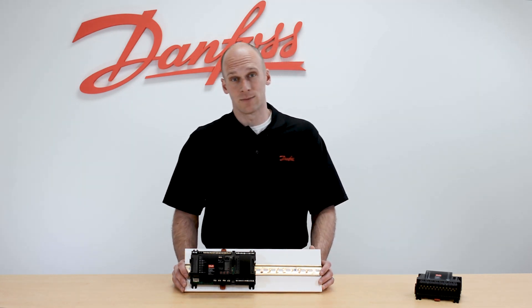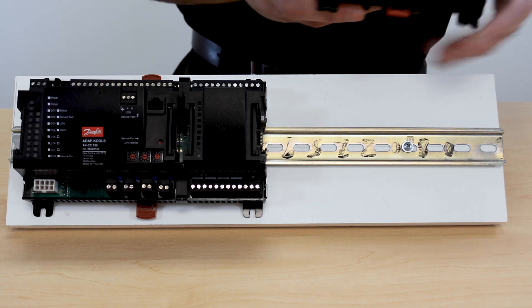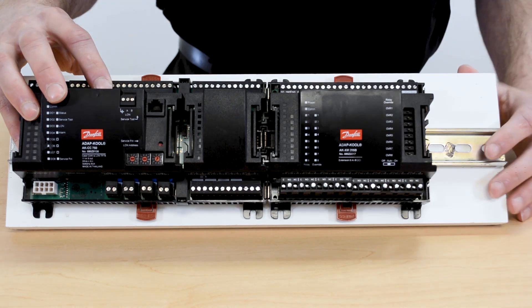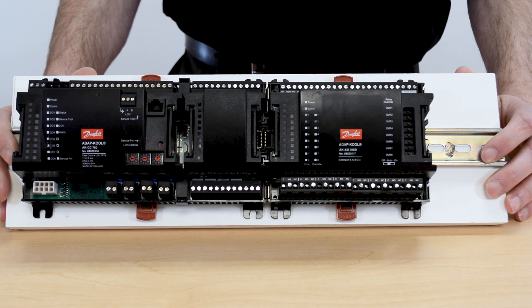The 11 inputs and 8 outputs may not be sufficient when you start to get into larger applications with 3 and 4 evaporators being controlled. In that scenario, we'll take one of our standard AK-XM modules, which can be attached directly to the end of the main 750 baseboard, and the additional control points on that extension module become part of the setup of the main 750 itself.